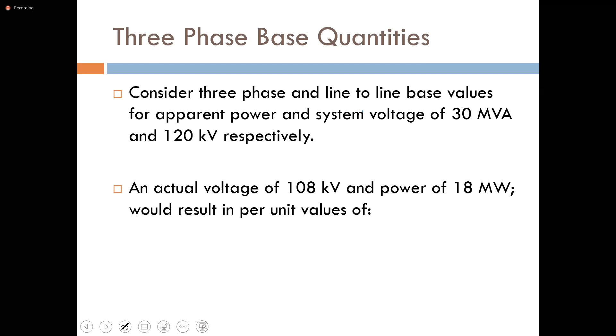The per unit values for these two: per unit voltage, remember per unit is actual over base. The base voltage here is 120, so the per unit voltage would be 108 over 120, which gives us 0.9. And the per unit power would be 18 over 30, which gives us 0.6.